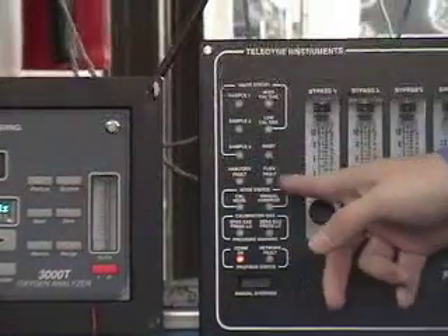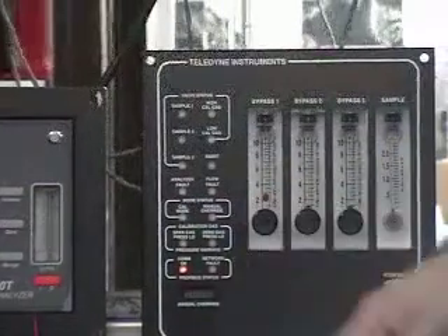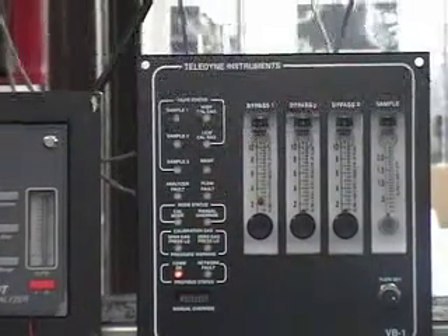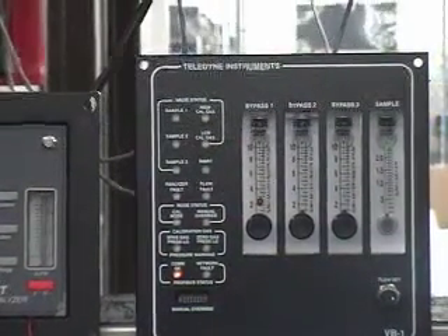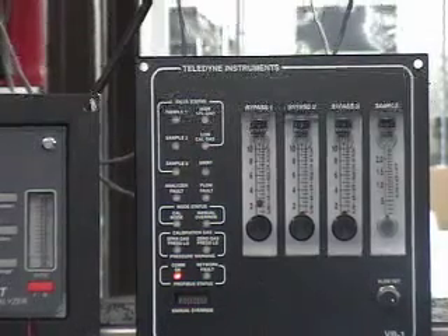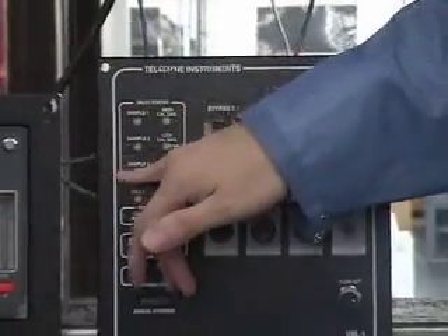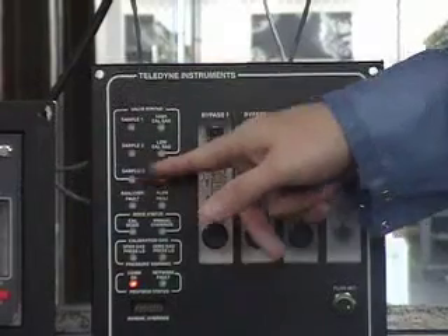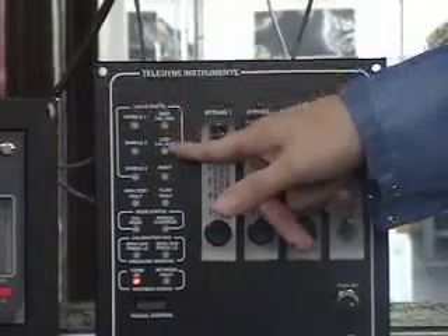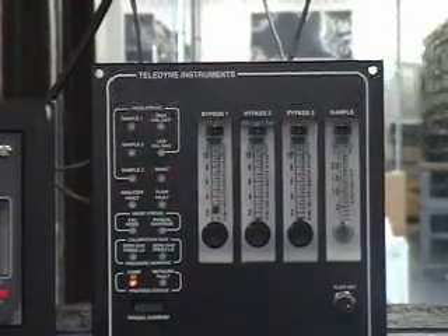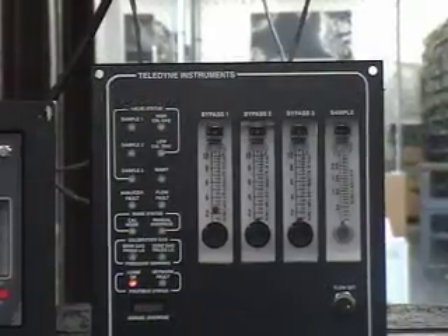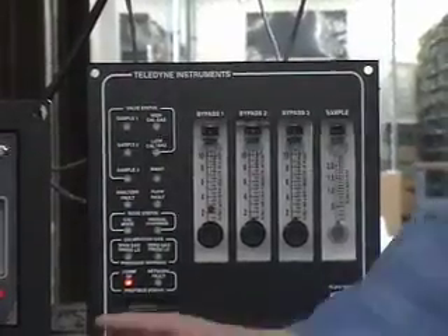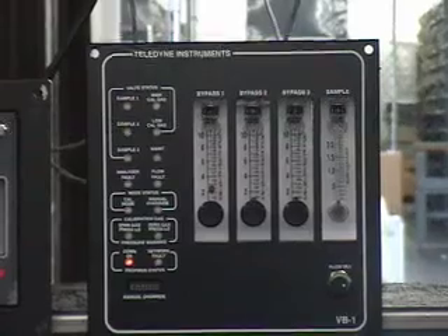There are no fault lights right now, but that's because I set it up so no fault lights come on. We'll make it so we get some fault lights later. And there is no valve open, no sample valve is open, all of them are closed. Even the calibration valves are closed. So that's how it boots up, with all valves closed. So I've got to send commands to open up one of the valves.